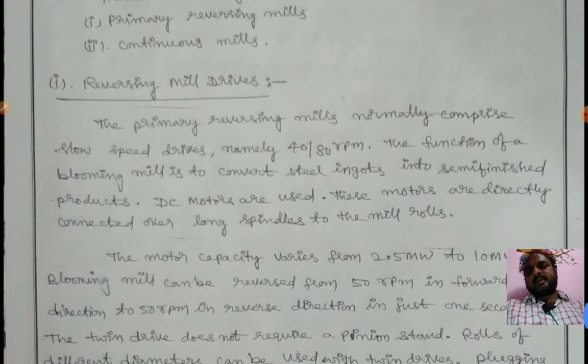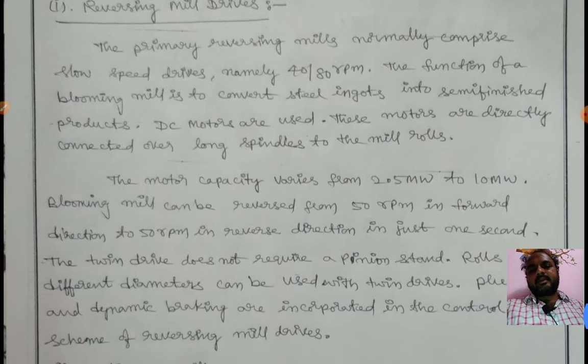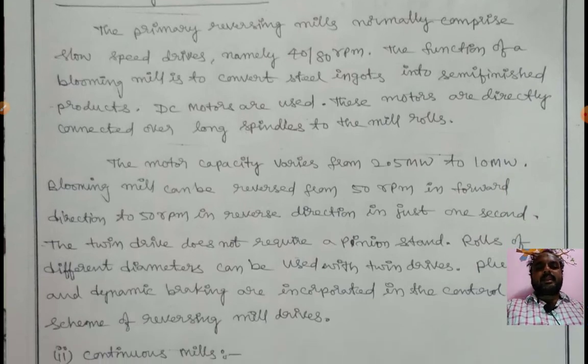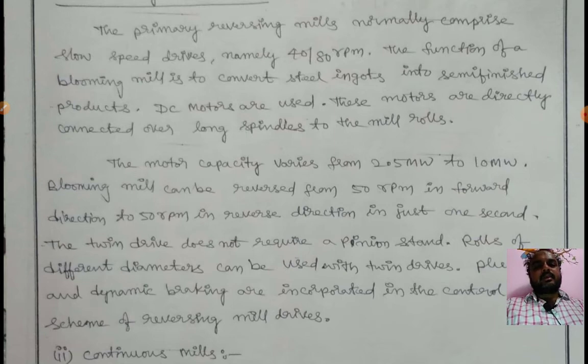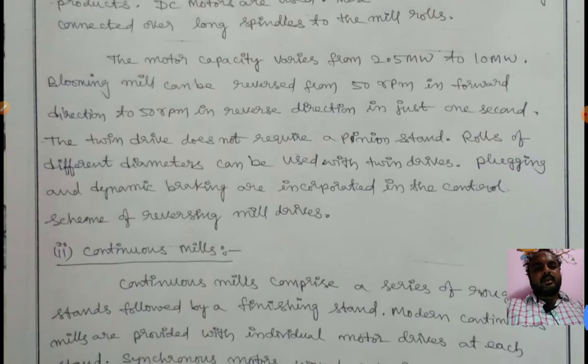Primary reversing mills normally comprise slow speed drives, normally 40 to 80 RPM. The function of the blooming mills is to convert steel ingots into semi-finished products. DC motors are used in this type of mill. These motors are directly connected over long spindles to the mill rolls.